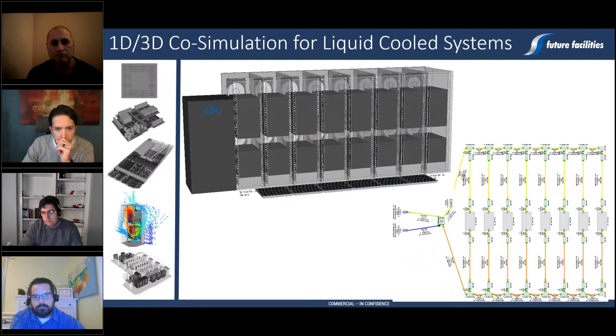This is helping us to keep our flow network very simple and easy to understand and easy to look at the results. We put 8 of these cabinets in a row that has 10 ACUs and a chilled water system that is providing chilled water for both ACUs and CDUs. In the flow network, you can see that the smaller purple boxes are representative of ACUs, and the bigger boxes are representative of CDUs.